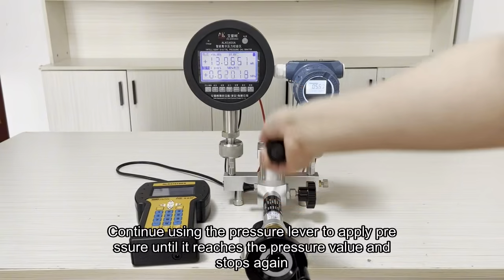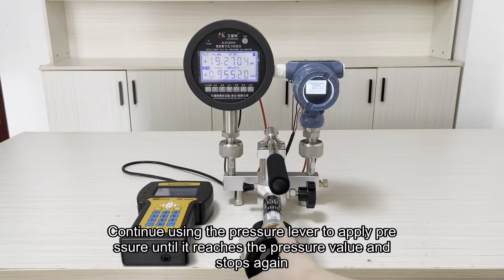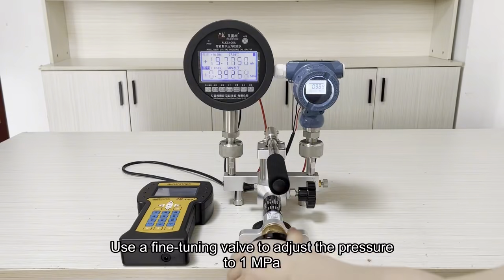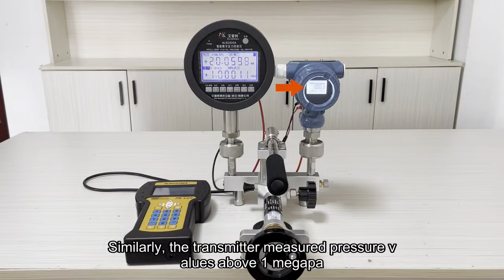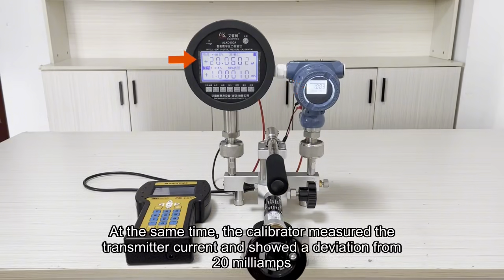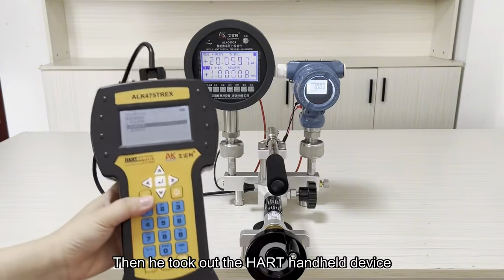Continue using the pressure lever to apply pressure until it reaches the pressure value and stops again. Use a fine-tuning valve to adjust the pressure to 1 MPa. Similarly, the transmitter measured pressure values above 1 MPa. At the same time, the calibrator measured the transmitter current and showed a deviation from 20 mA. Then take out the HART handheld device.